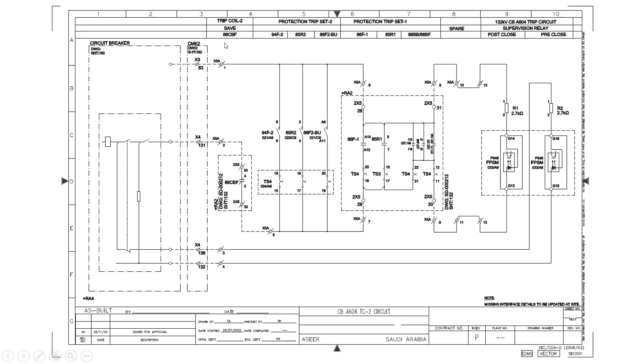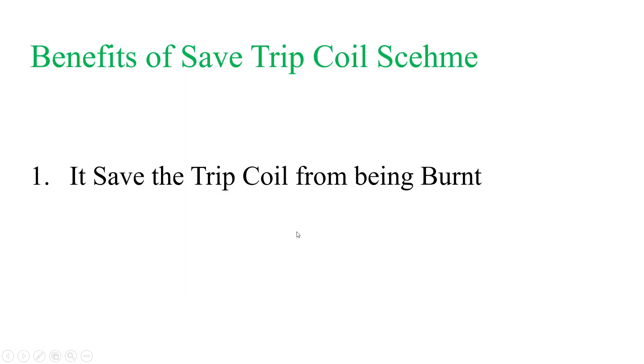This is the Trip Coil 1 and 2 save scheme and it is very helpful to save our coils. The benefit of the Save Trip Coil scheme is that it saves the trip coil from being burnt in case of a circuit breaker failure condition, where the breaker is receiving a continuous positive pulse but is not operating. The CBF NC contact will open and save the trip coils. Thank you for watching.